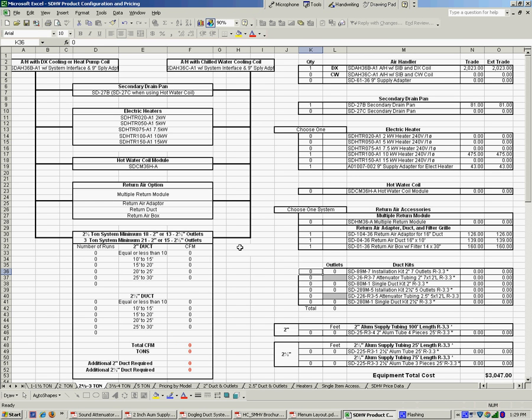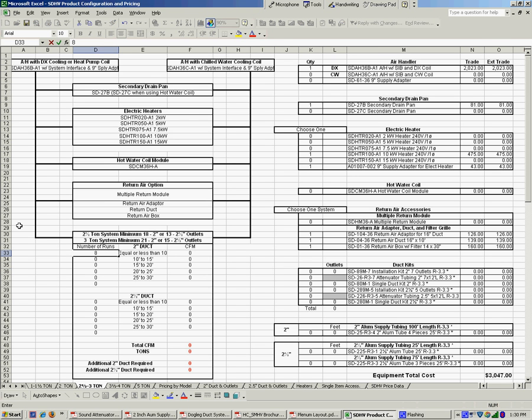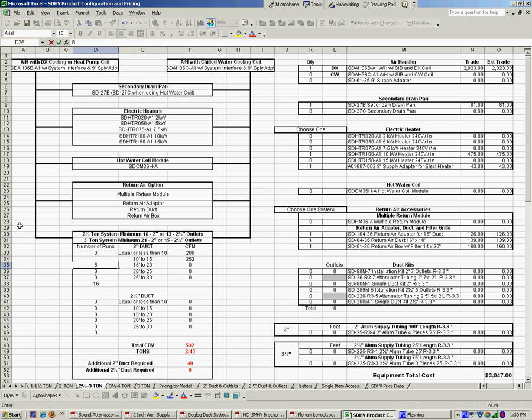The next step is probably the most critical. It's going to tell us what is the duct design that we're going to have to use on the system. So we look at it and say, okay, I'm going to need 8 outlets that are less than 10 feet for the job. I'm going to have 8 outlets that are 10 to 15 feet from our plenum design. And then I'm going to have 8 outlets that are between 15 and 20 feet. That was back from that design where we looked at the plenum and where the individual register is going to be located.